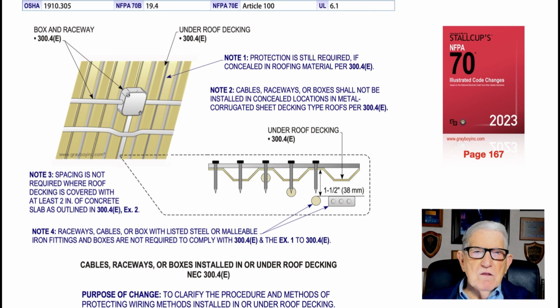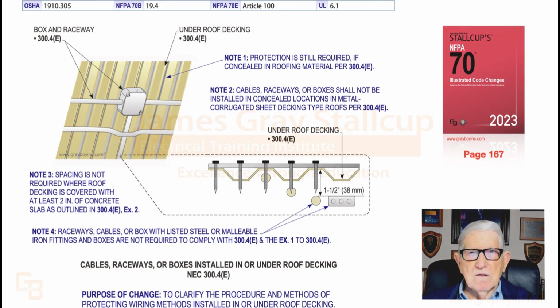And then, of course, the rest of note 1 and note 2, along with note 4, is just giving you information about this 1.5 inch setoff below a flat roof area, and mainly, be on that ridge, and usually you're in pretty good shape. And then note 4 says raceways, cables, or boxes with listed steel or any kind of iron fittings and boxes are not required to comply with 300.4(E) and the exception 1 to 300.4(E). And that's what this illustration is illustrating to the user of the NEC.